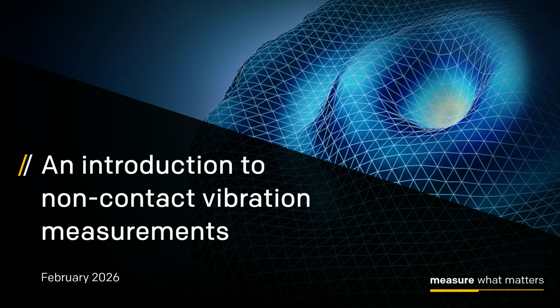Yes, what are the possible sources of errors in displacement measurement and/or calculation from velocity information in the sweep scenario? Frankly, there's nothing special about displacement, because if you are after displacement, then you just go pure displacement. I guess this comes from the fact that in the past people used only velocity and integrated velocity to displacement.